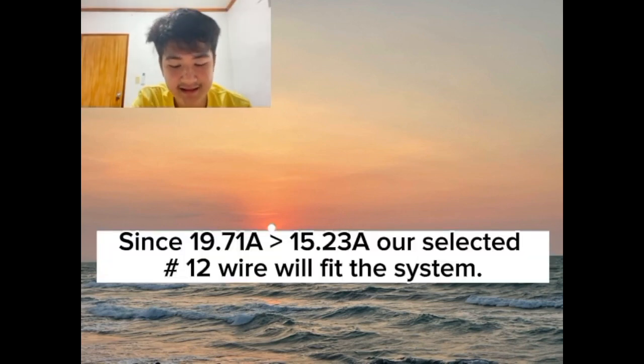Since the 19.71 ampere that we got is greater than the 15.23 ampere we got in step 2 earlier, our selected wire is the number 12. It will fit.